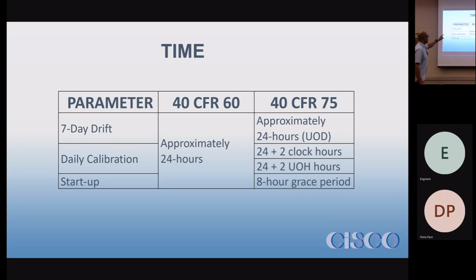So the first issue is time of doing a calibration. Both Part 75 and 60 in general talk about you want to have your calibrations about 24 hours apart. Obviously, Part 75 gives you kind of a 2-hour grace period. So you have 26 clock hours or 26 unit operating hours, depending on it, if you're using offline calibrations, which we'll get into as we move along.